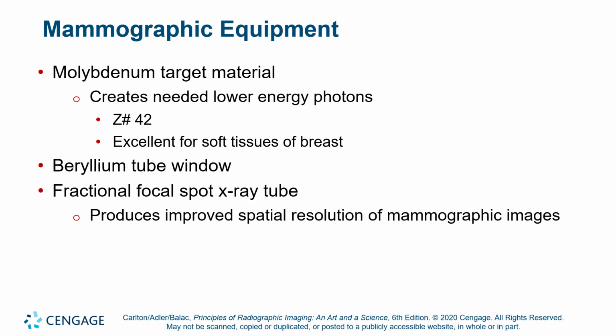The beryllium window is needed because we can't use a conventional Pyrex window, as it absorbs too many of the soft X-rays, and we need lower energy. So the X-ray techniques for mammography are somewhere around 20 to 25 kVp, as compared to diagnostic imaging where we start with 50 for a hand. Well, there's not supposed to be any bones in breast tissue. There are sometimes calcified granules and calcified deposits in breast tissue, but that's the exception, not the rule.